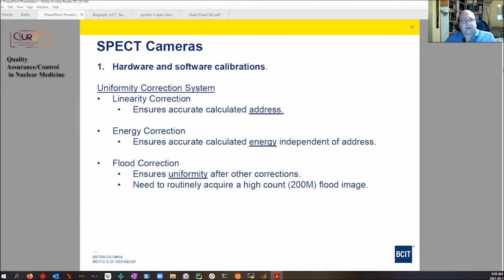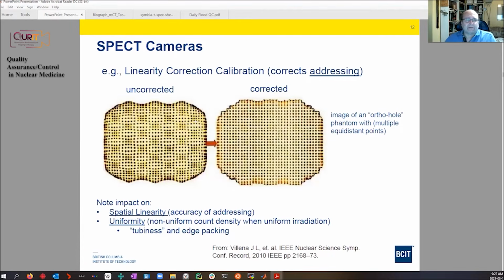The third correction is what we call a flood correction, just sort of a cleanup. It is a correction that cleans up any non-uniformities after the other two corrections. We routinely recalibrate it by doing a high count, 200 million count flood. So here's an example of what we're looking at. This is a nice paper from an IEEE symposium.